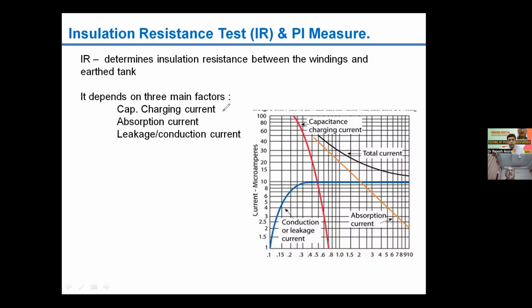Basically, first is the insulation resistance measurement and then the polarization index. The polarization index is nothing but the ratio of two insulation resistances, one taken after 10 minutes and another taken after 1 minute of measuring. So the two values of insulation resistance are recorded and the ratio is calculated; because it is an index, it has no unit.